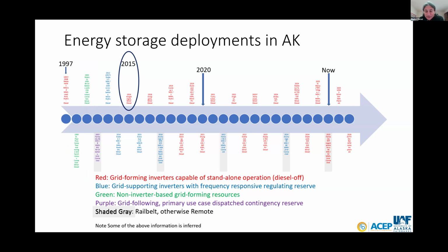2015, I'd say, was the first wind diesel system with a true grid forming battery. First wind diesel system with a grid forming battery - this was in Quinhagak, followed shortly after in 2018 in Kongiganak. This used a grid forming ABB PCS 100 grid forming battery in a wind diesel system, and was able to go diesel off. That developer, Intelligent Energy Systems, has about a half dozen wind diesel systems right now capable of diesel off with a grid forming inverter, scattered throughout the region.